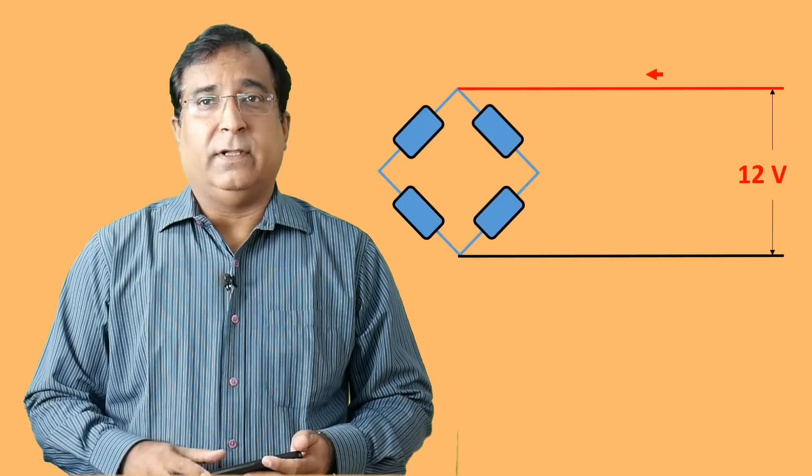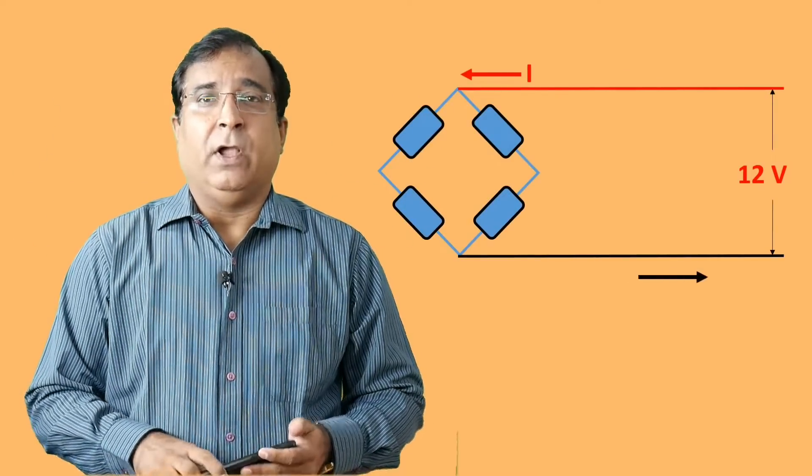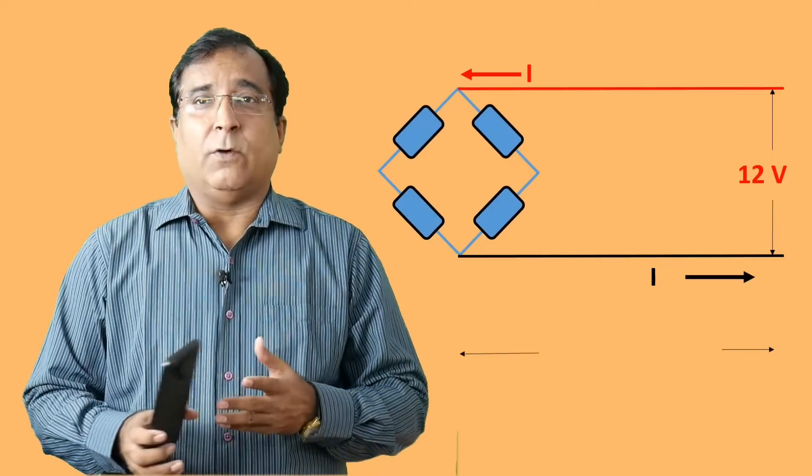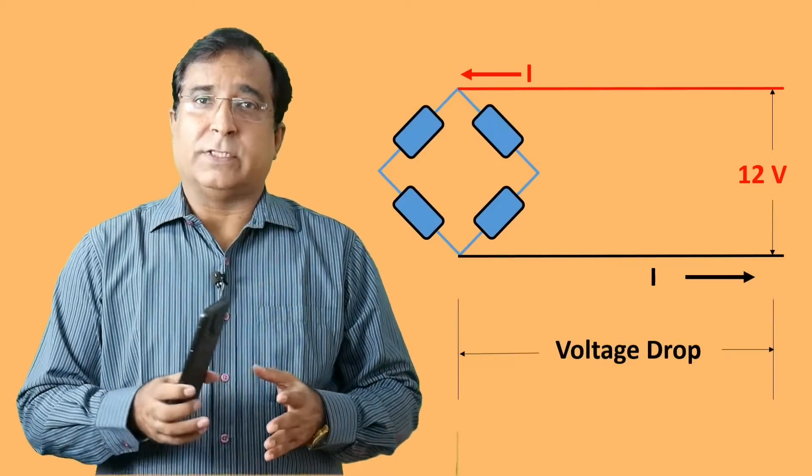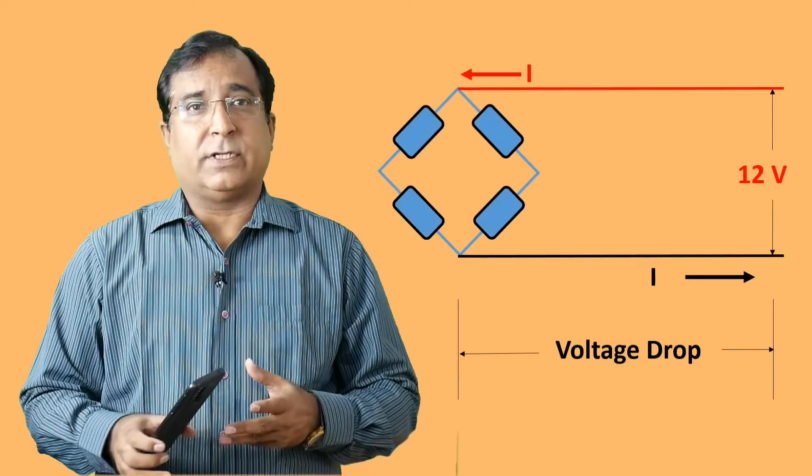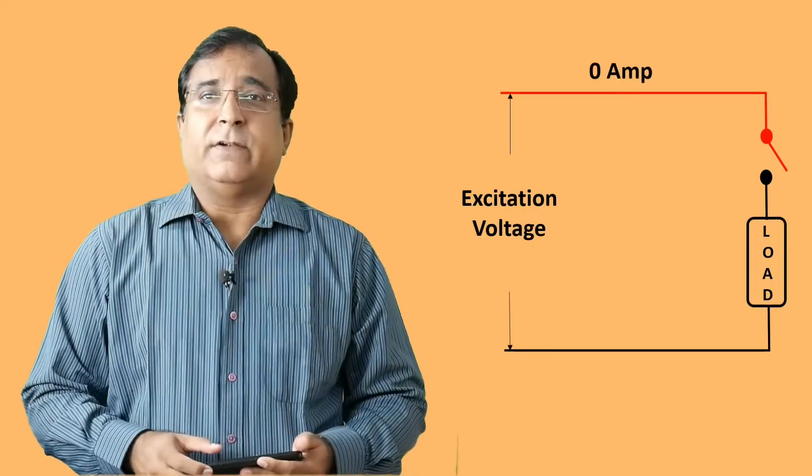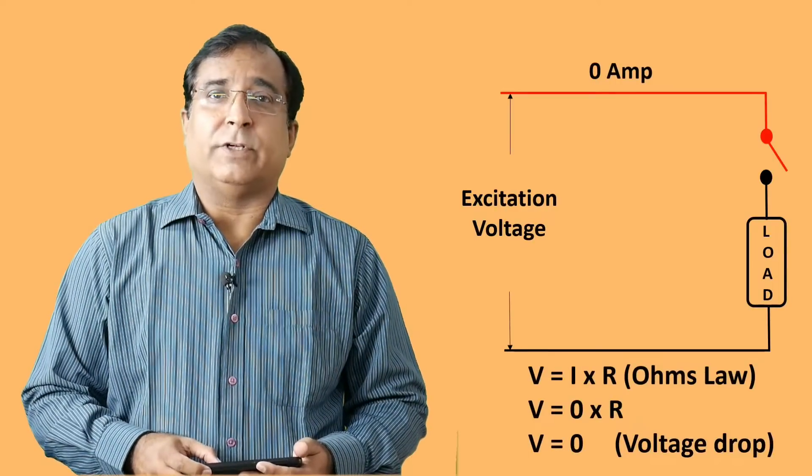As long as there is no weight applied on the load cell, its Wheatstone bridge is balanced and the signal output is considered to be 0 millivolt. As soon as you put a load on the load cell, the bridge gets unbalanced and a millivolt signal output is generated and it causes current to flow in the bridge circuit. Now as per Ohm's law, this current flow causes a considerable voltage drop across its cable length. Resulting you get a less excitation voltage than it is supposed to be.